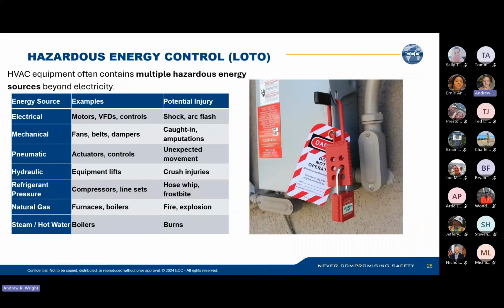All right, hazardous energy control, or LOTO, lockout, tagout. HVAC equipment often contains multiple hazardous energy sources beyond electricity. So what are they? Electrical is the obvious one, your motors, your controls. You also have mechanical: fans, belts, dampers. You have the potential for caught-in and amputations.